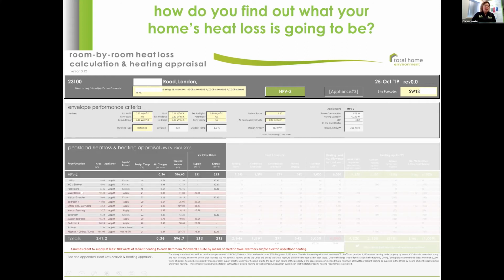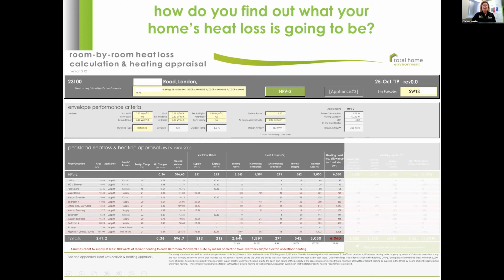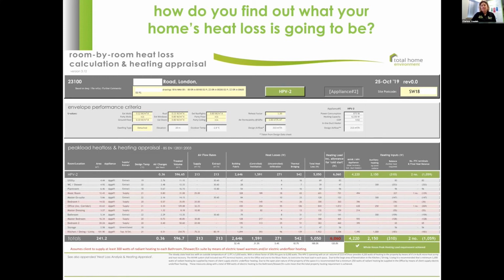And down here on the left, we've got each room and what its area and volumes and airflows need to be. And then here we're getting down to the nitty gritty of the heat losses. And here we've got a figure of 5 kilowatt heat loss for the whole house. However, that's not the figure that we're going to be looking at, because you need to be able to have your house warm from a standing start, from when nobody's been in there for 3 months. So here, that's been added, and the whole house heat loss for this particular building is 6 kilowatts.